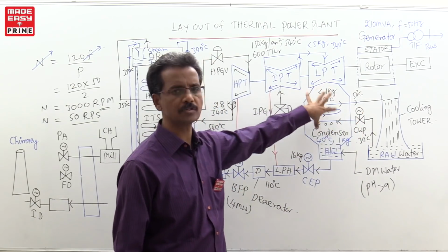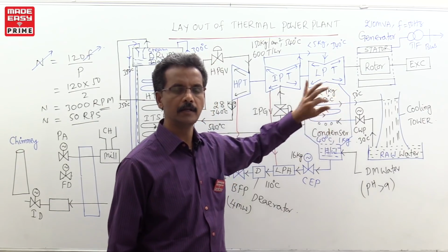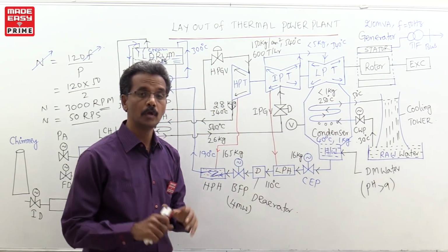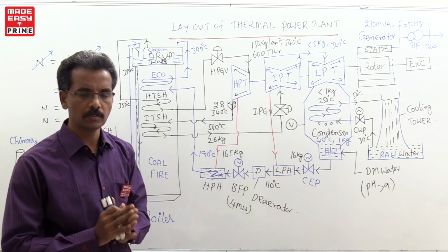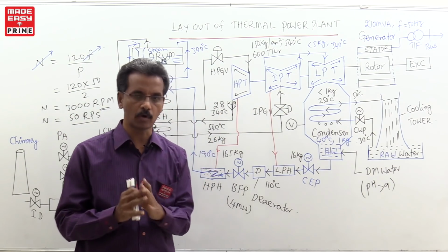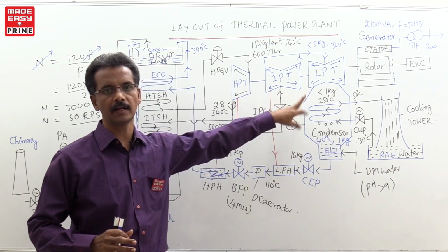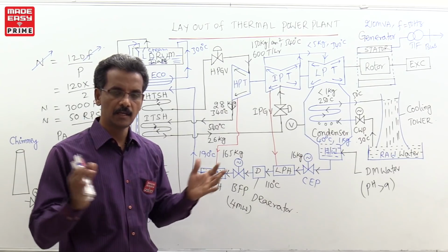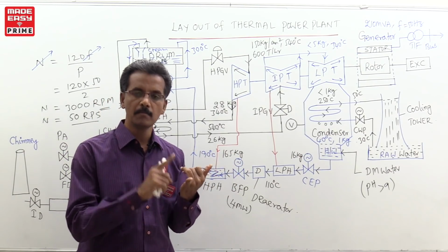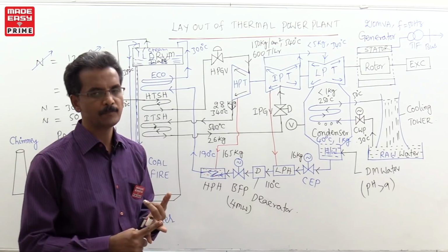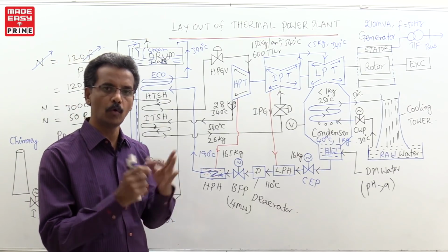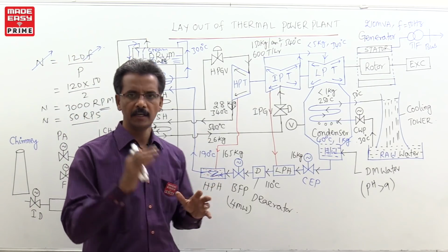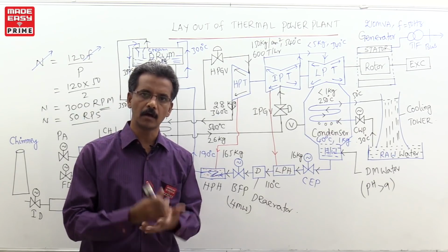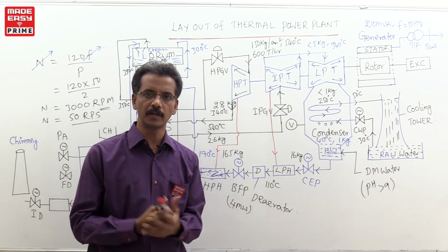This is the area where most of the energy is wasted in the thermal plant. That is why, from the thermal efficiency point of view, boiler efficiency is high, main generator efficiency is high, but turbine efficiency, because of the condenser, is less. If you take overall efficiency, it is the multiplication of boiler efficiency, turbine efficiency and generator efficiency. Overall efficiency of the thermal plant is normally 38 to 39%, or you can think of around 35 to 40%.